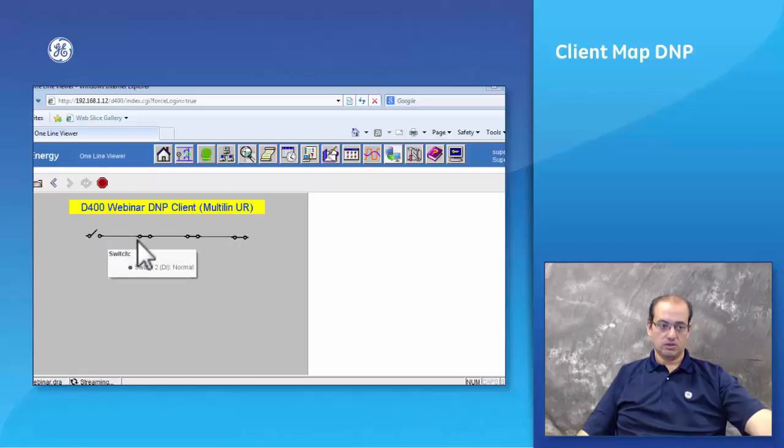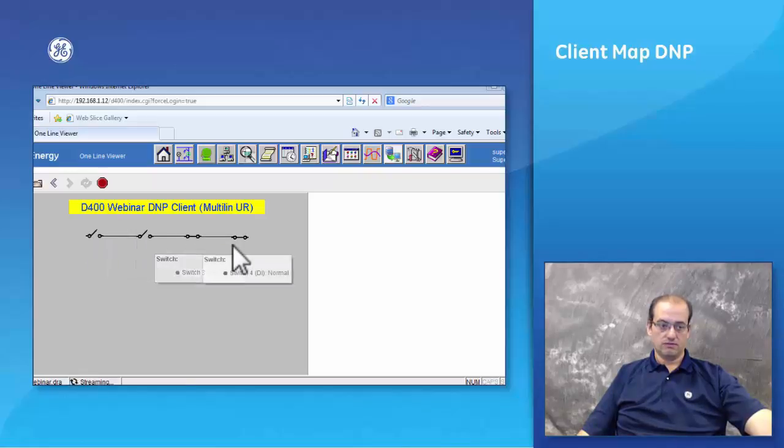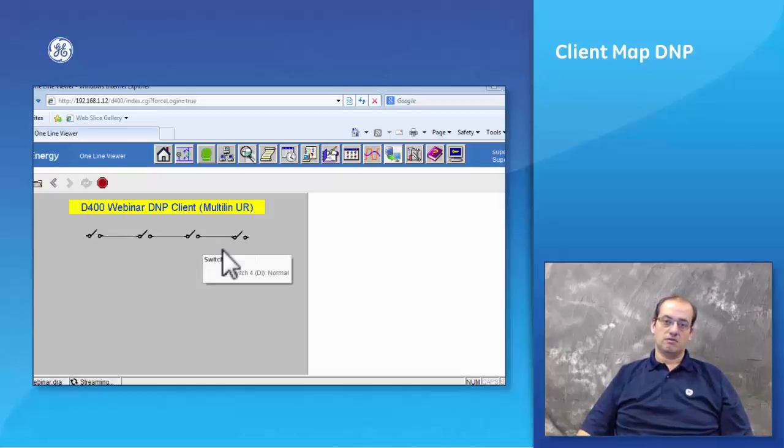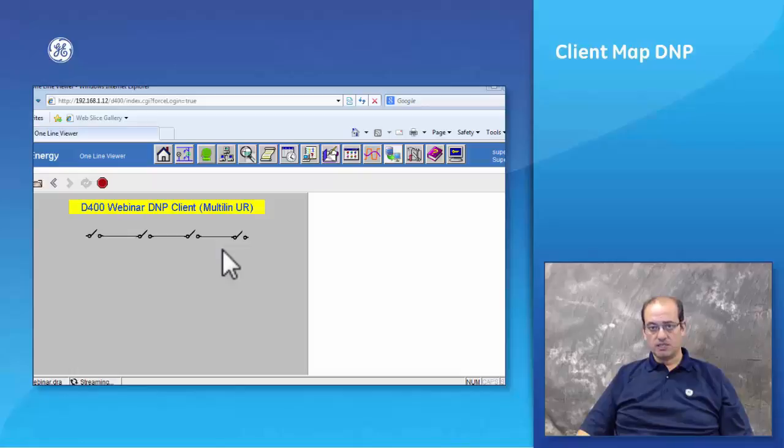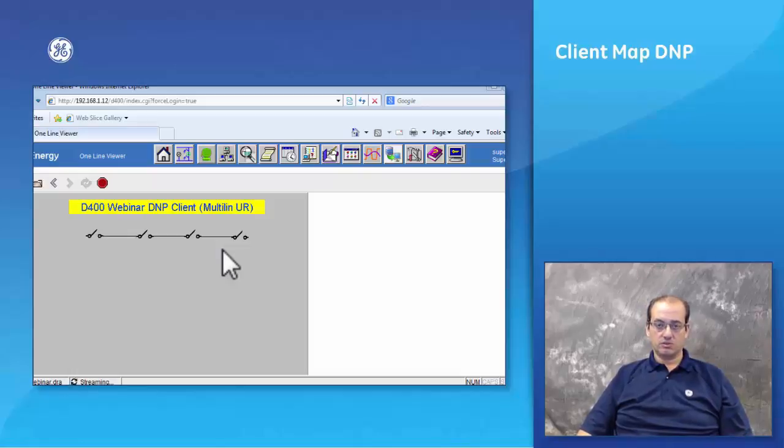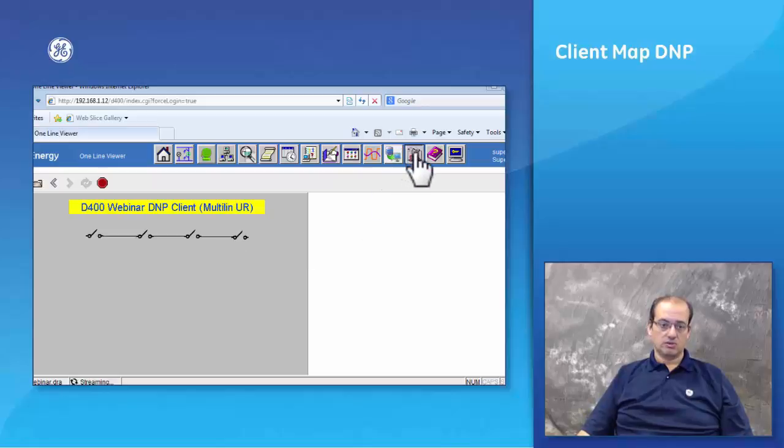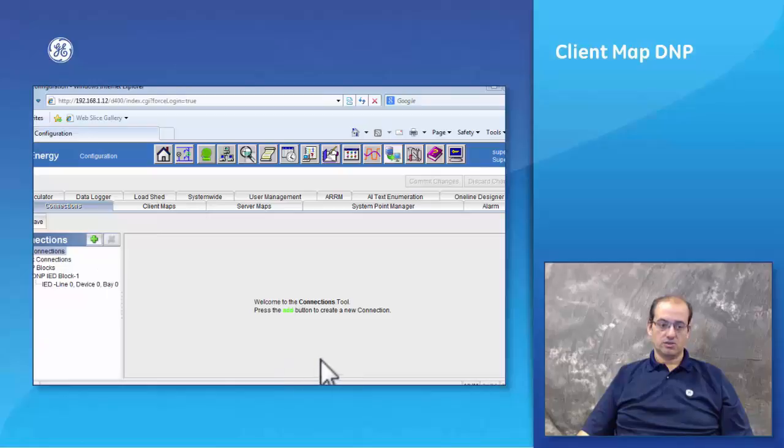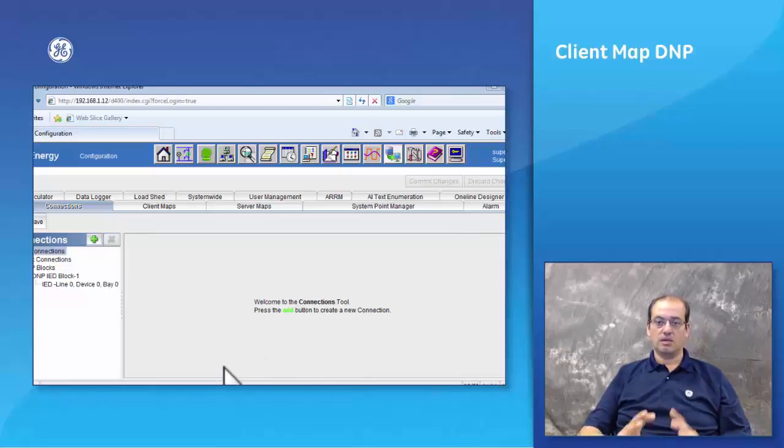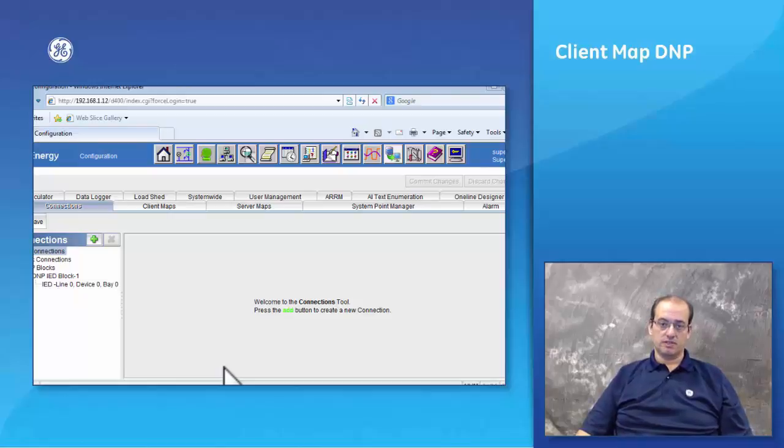Hopefully this gave you a very good understanding of the client map table and how this client map can be used for every other device. When you add another device to your substation which has the same criteria, you don't have to create the client map again. You can reuse the client map and just go under your configuration, under your connections, add an extra connection, use the same client map, and that client map becomes a template that you can always use for the same device.